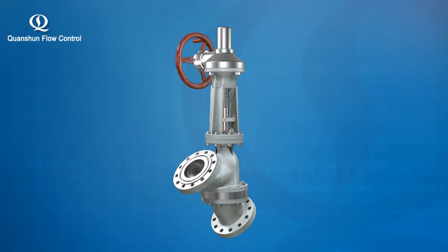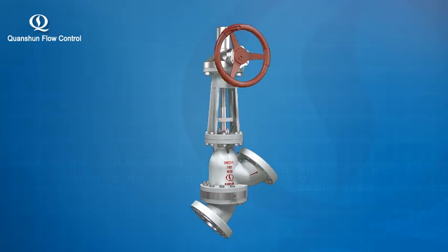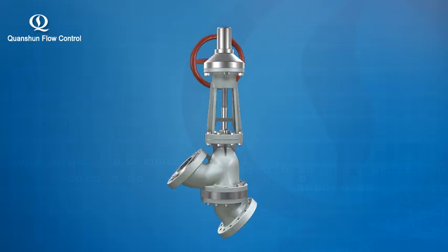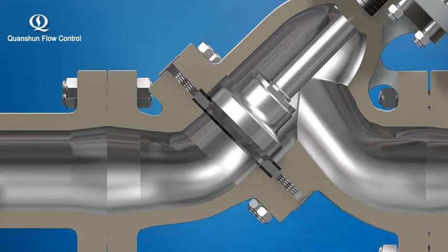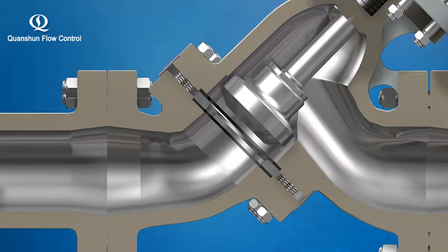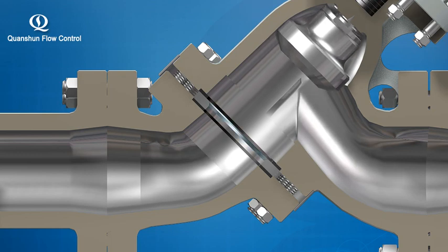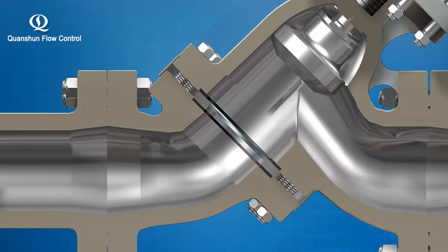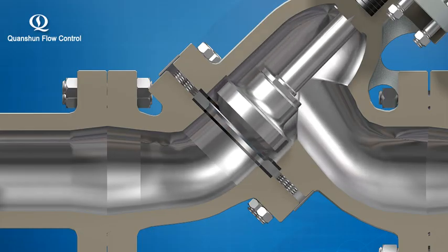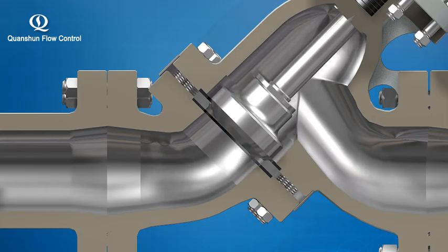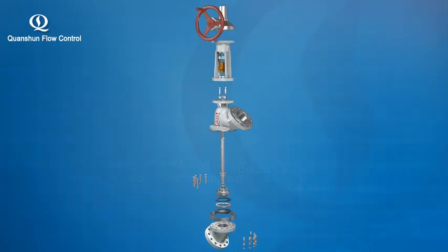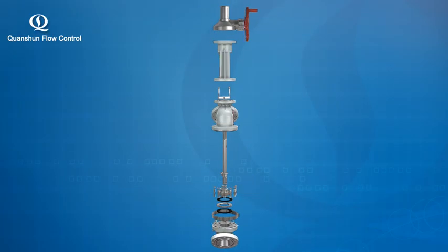Based upon the absorption of overseas proprietary technologies, we've made significant improvement with respect to the surfacing materials used on the seal face. The seal face uses cobalt-based high alloy material for plasma arc surfacing, whose hardness, via heat treatment, is adjusted to the optimal state that can best resist the wash, erosion and impact, increasing the seal face strength by at least twice the strength of general valves.